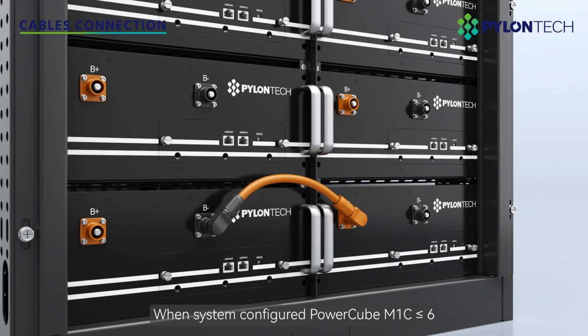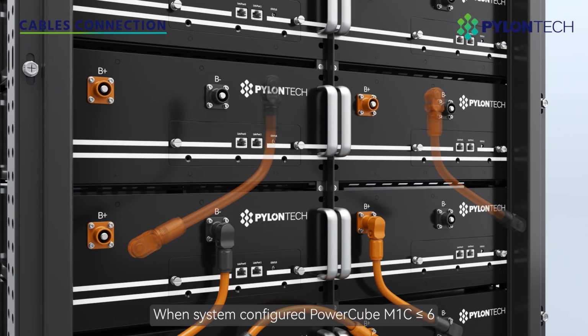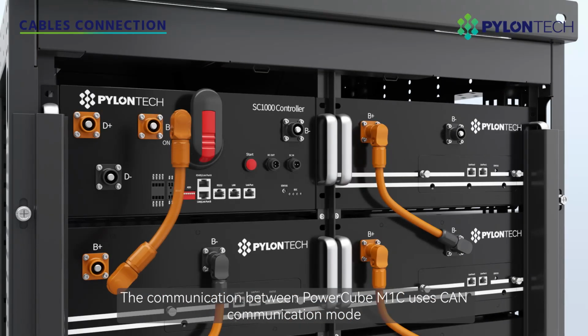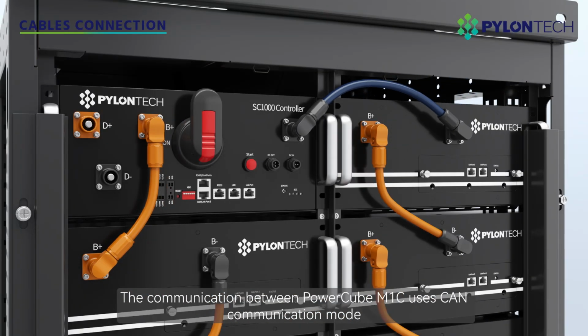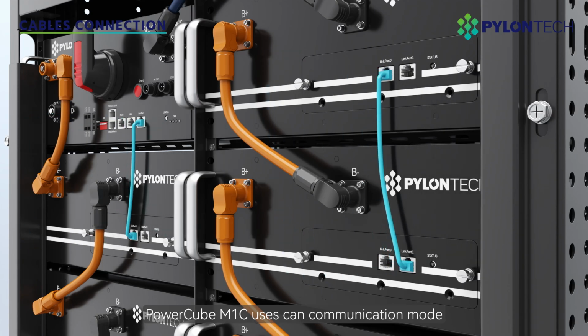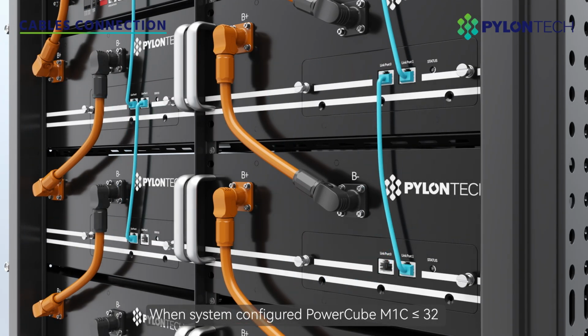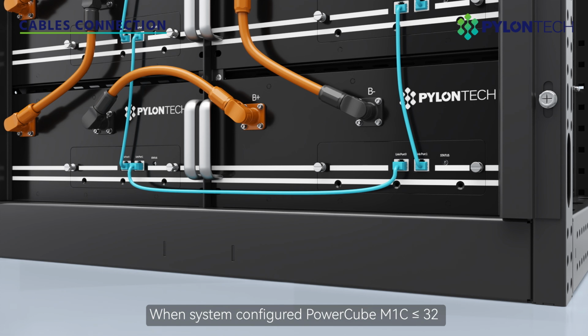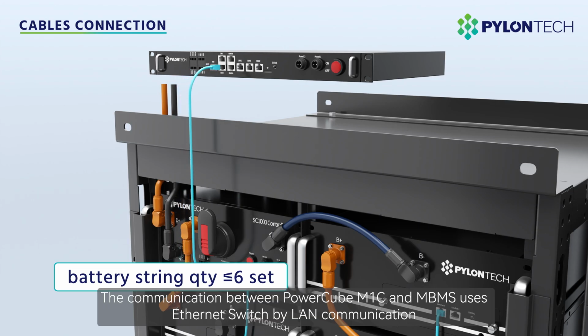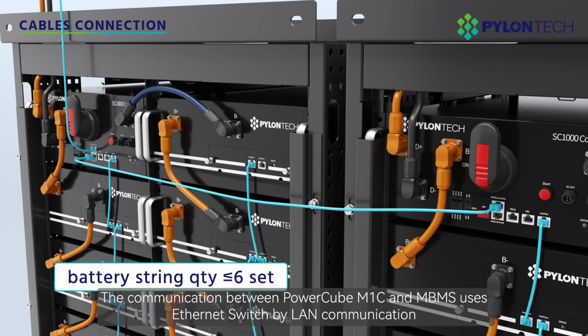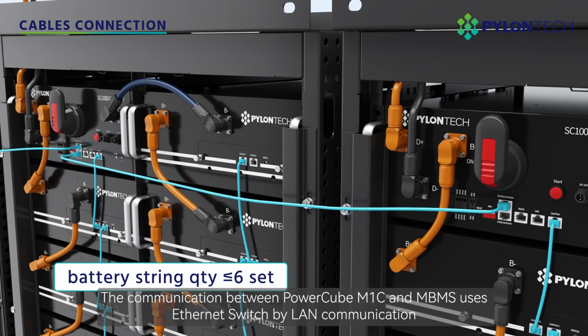When system configured, PowerCube M1C less than or equal to 6. The communication between PowerCube M1C uses CAN communication mode. When system configured, PowerCube M1C less than or equal to 32. The communication between PowerCube M1C and MBMS uses Ethernet switch by LAN communication.